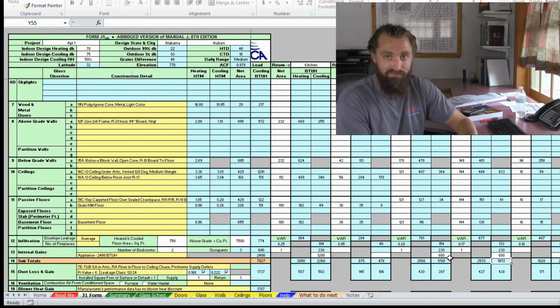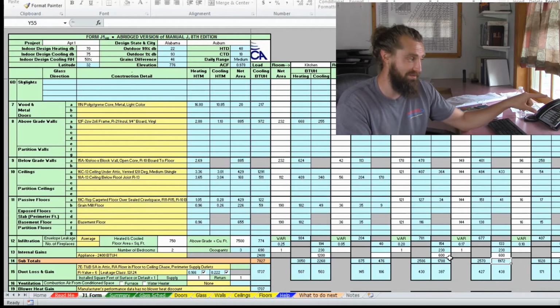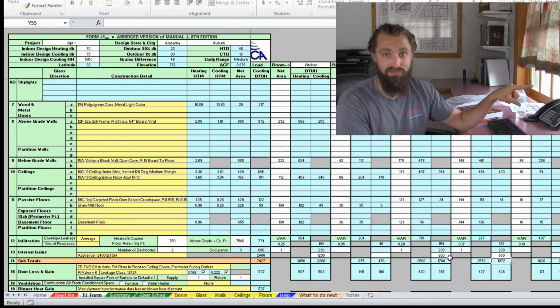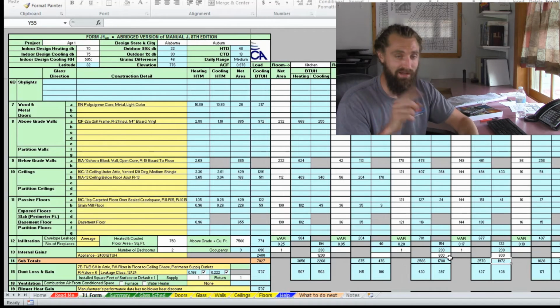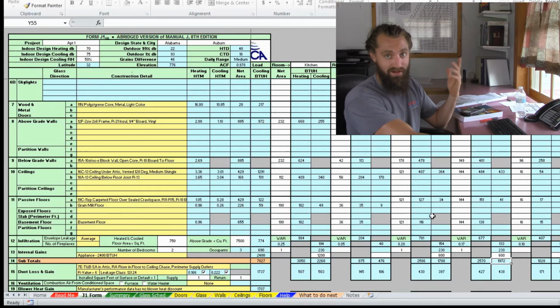So we're going to have to go back out and modify the system to allow more air into that room to account for the BTU load from these gaming computers. Keep that in mind when you're looking at houses, bedrooms, and even office spaces.